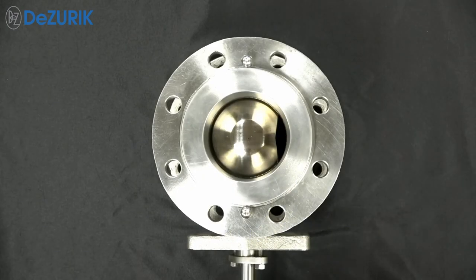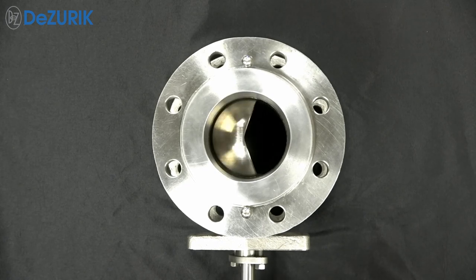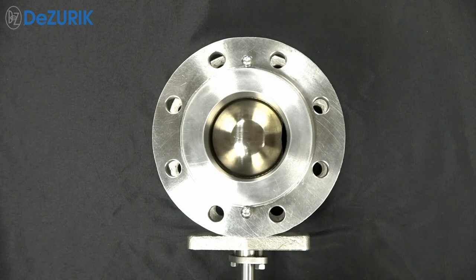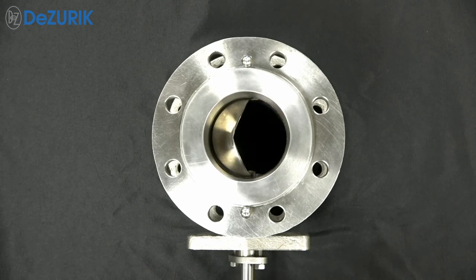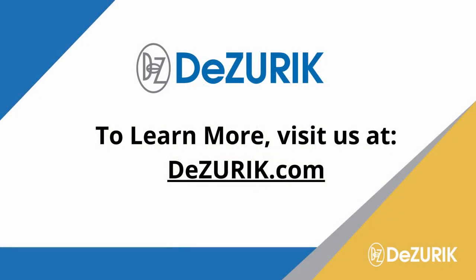With all brands of V-Port ball valves, alignment and loading of the seat against the ball is critical to provide proper shutoff capability and to minimize friction that can increase the force required to operate the valve. Increased operating force can significantly degrade control valve performance and reduce valve life. DeZURIK's V-Port ball valve, with its non-threaded seat retainer, drop-in-place self-aligning seat, and controlled seat compression, minimizes the required valve operating force, providing superior control and ease of maintenance.